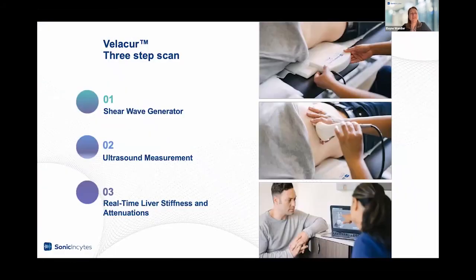There are three basic steps to how Velacur works. In the top picture, you'll see what we call an activation pad or unit that's placed under the patient's back. This unit gently vibrates, creating waves through the liver, which are then measured by ultrasound, as shown in the middle picture. The results are immediate and provide measurements of liver elasticity and attenuation, which are surrogate measurements for fibrosis and fat.